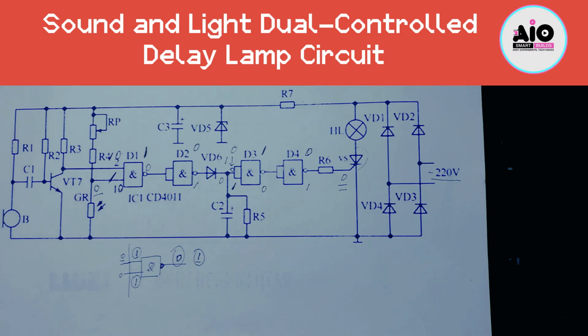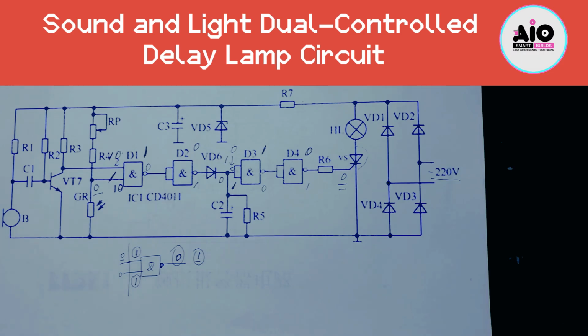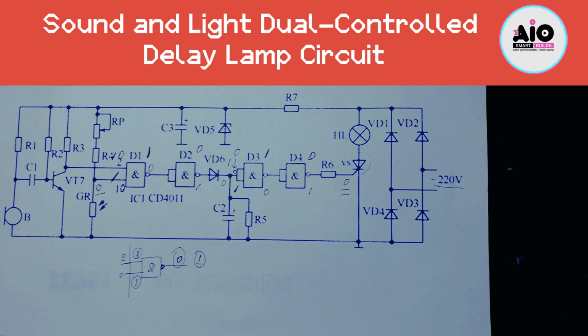The advantage of this circuit is that it only needs to be connected with two wires, that is, a two-wire circuit, and the switch can be directly connected to a standard box, such as an 86 switch box. It can be used directly without the need for a separate neutral line. Its disadvantage is that it cannot control relatively high power circuits and inductive loads, as well as dimming circuits.